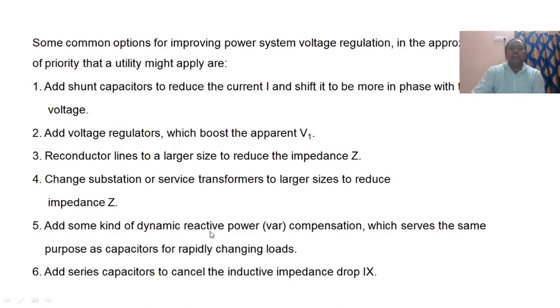Add some kind of dynamic reactive power, that means VAR. VAR is volt-amp reactive compensation, which serves the same purpose as capacitors for rapidly changing loads. Rapidly means sudden changing loads, the sudden variations in the loads. Add series capacitors to cancel the inductive impedance to reduce the drop IX. The main aim is to decrease the magnitude of current by adding the shunt capacitors or series capacitors.